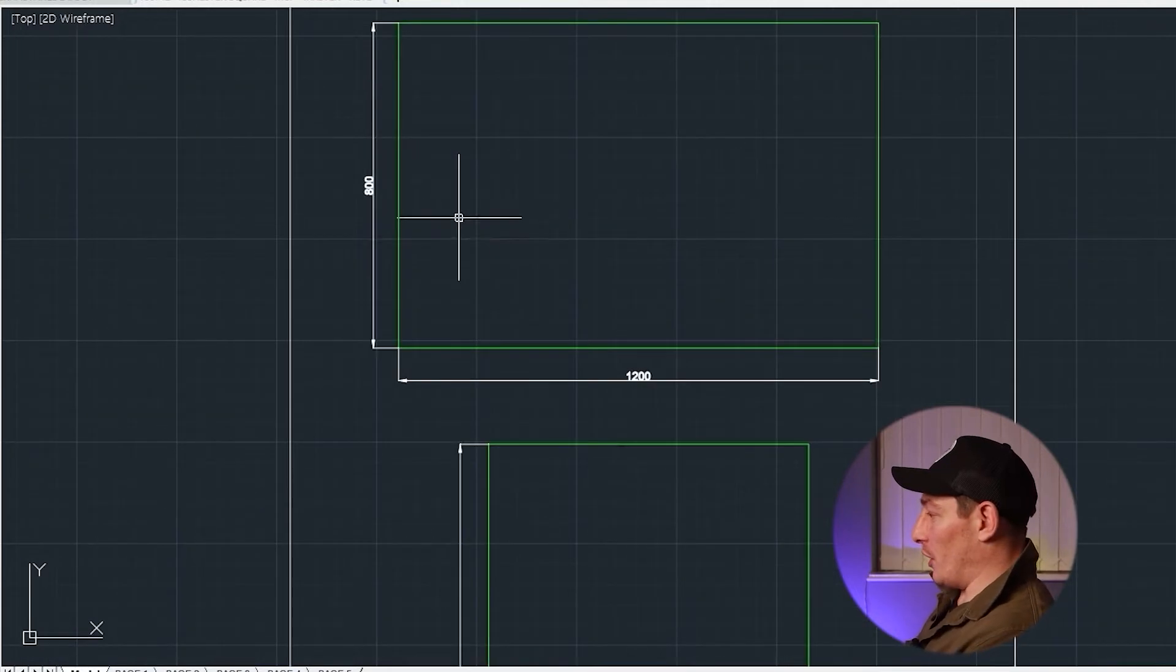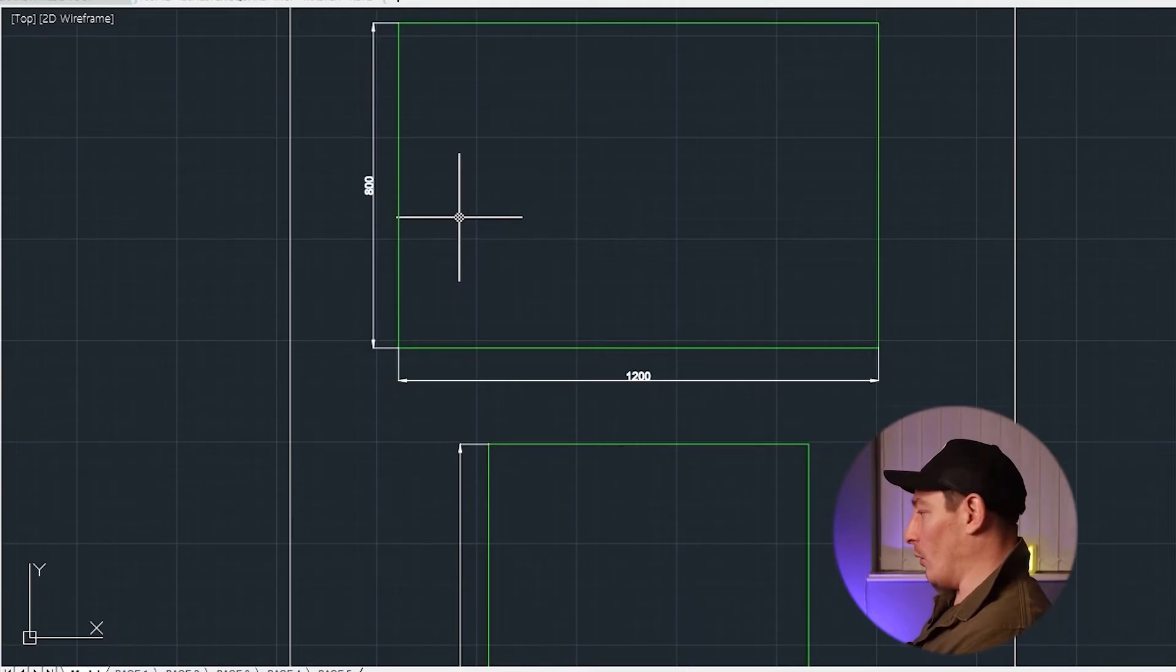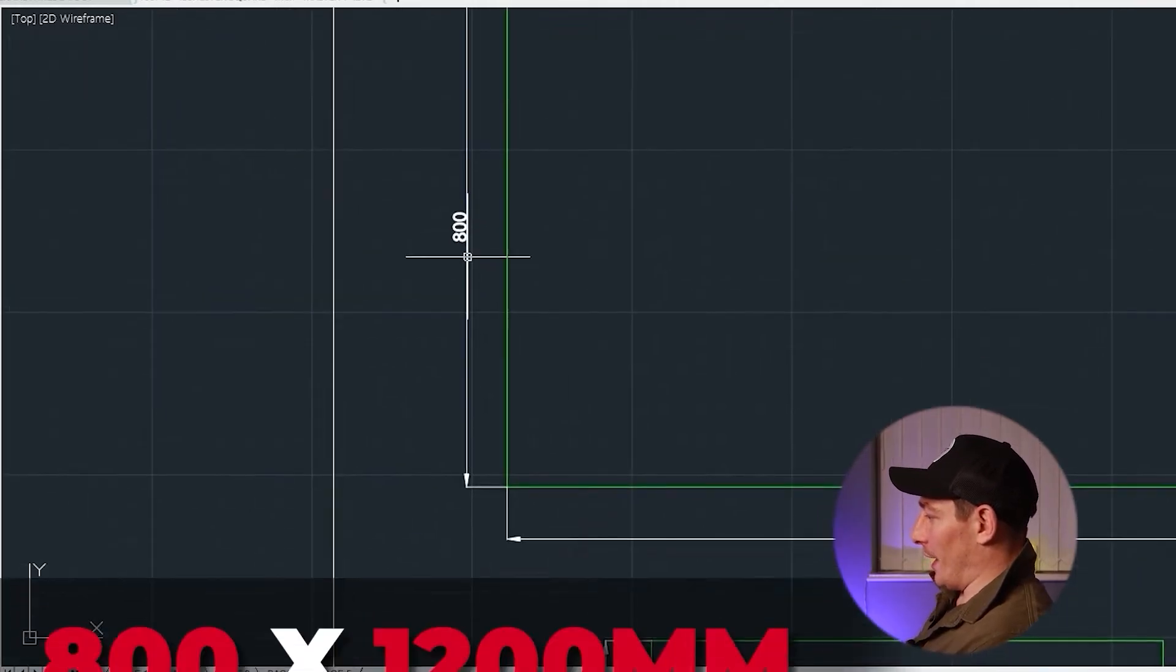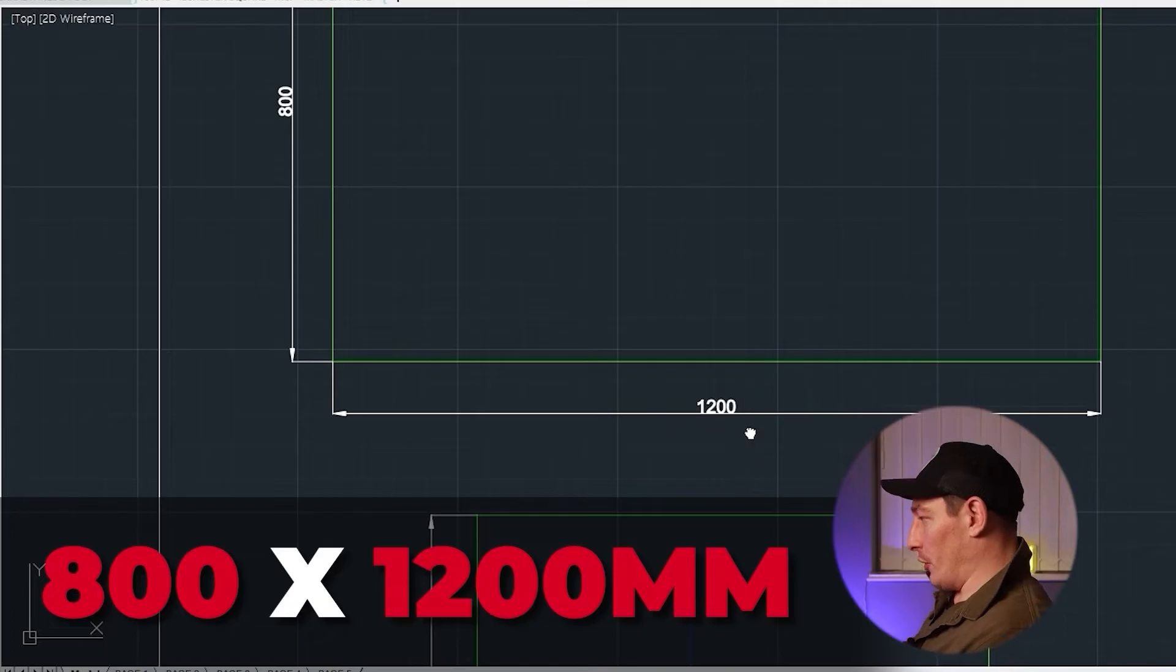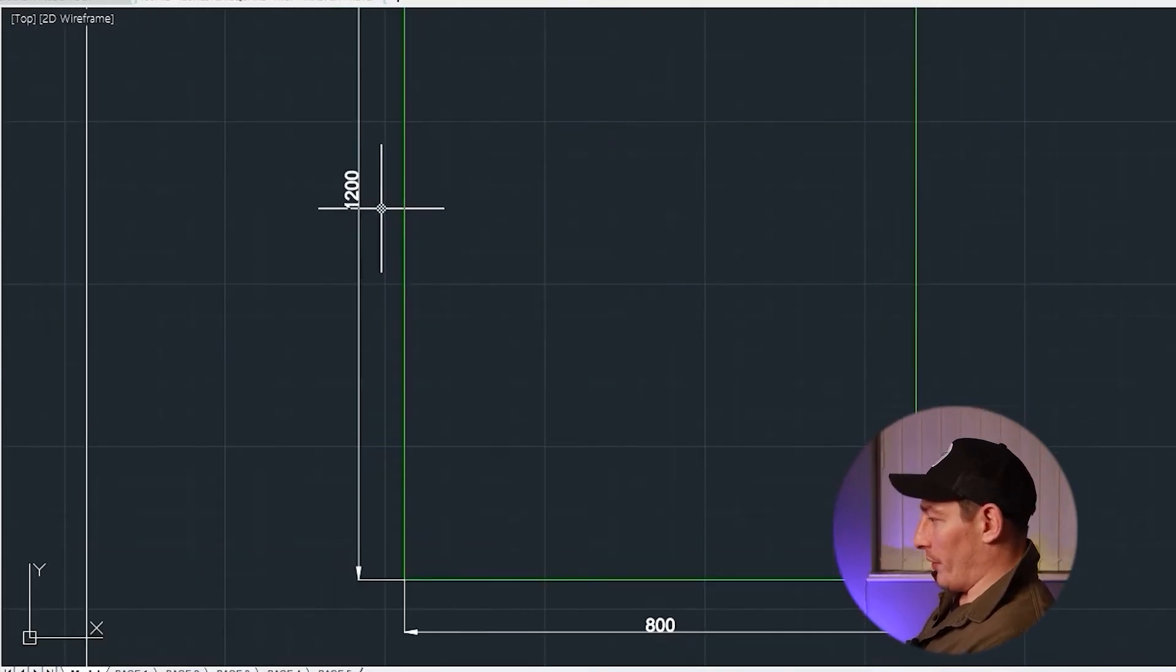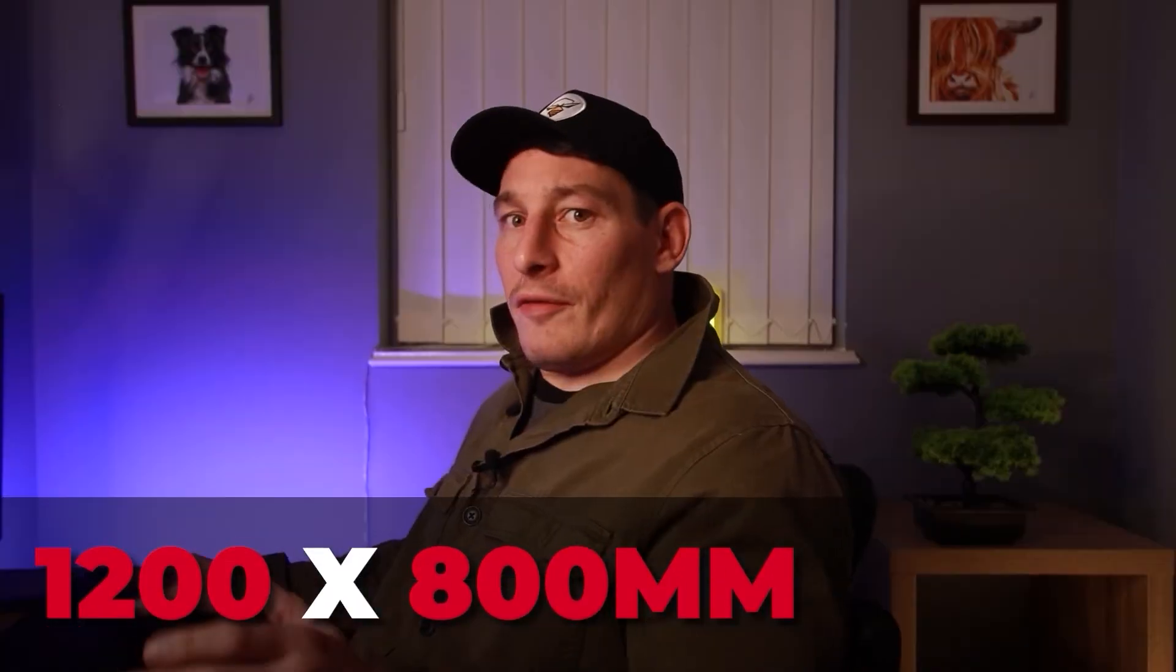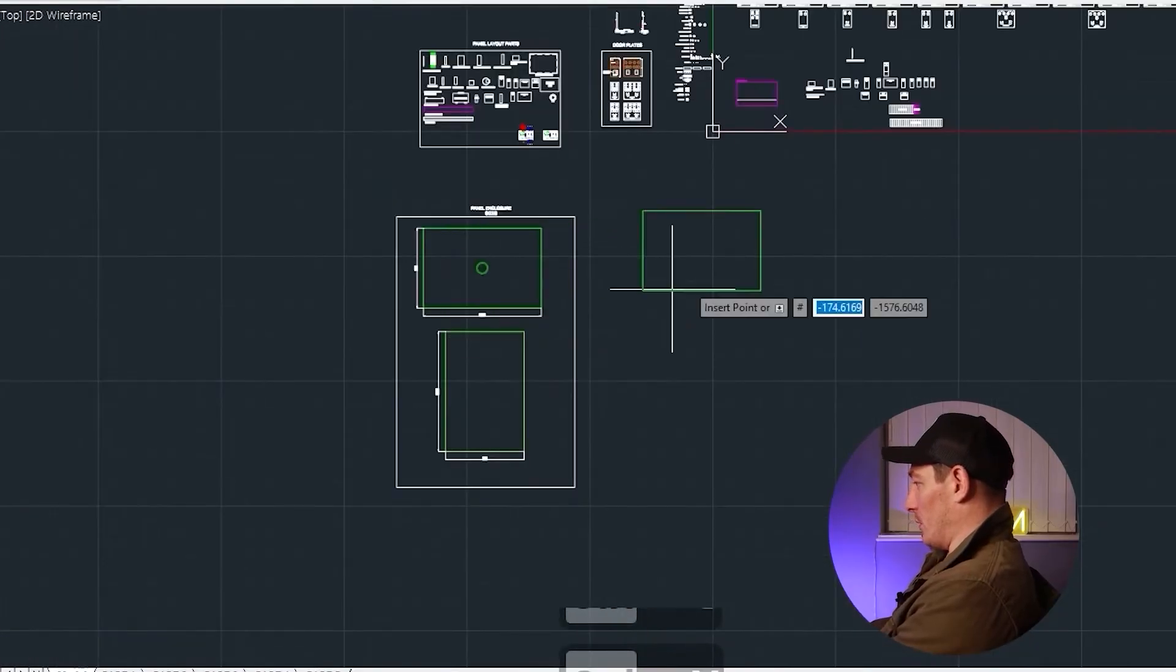The two enclosures that I've worked with most for BMS systems over the last couple of years are the same sized enclosure in a horizontal format or vertical format. So either 800 by 1200 or 1200 by 800. So for a project this size, that's the enclosure that I'm going to start with, and if I need to spec up from there I can, or if I need to downsize it then I can.